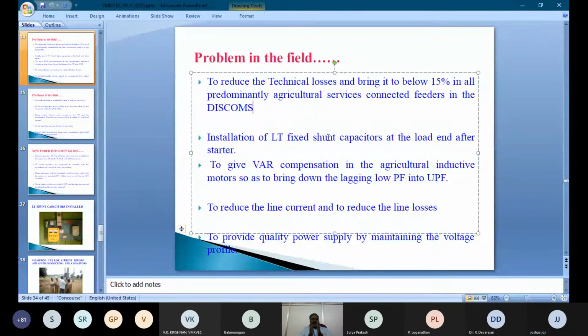we install meters, and these meters measure the instantaneous power factor and the average power factor also. The consumer has to maintain the power factor at unity or nearly 0.995. But practically it is difficult. Sometimes it is 0.85, and that is okay. But if the average power factor is below 0.85, we impose a penalty on the consumers. So whenever we take the bi-monthly or monthly reading, we register the average power factor also. If the consumer does not maintain the power factor at unity or 0.9 and above, we impose a penalty if it goes below 0.85.